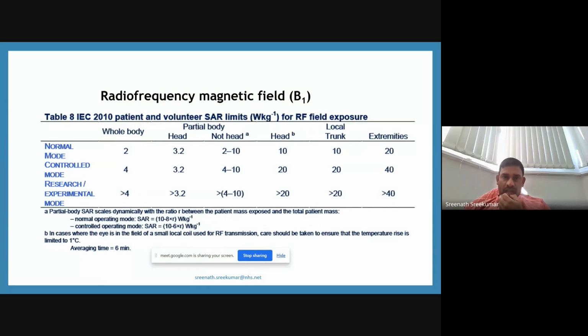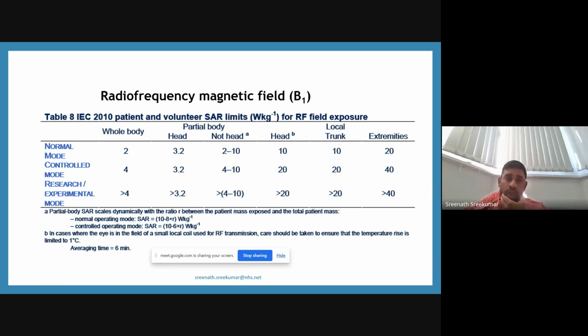So these are the radio frequency magnetic field modes. We have normal mode, controlled mode and research mode. The whole body SAR level, which is the specific absorption rate, is 2 watts per kilogram in normal mode, 4 watts per kilogram in first level mode, and above 4 watts per kilogram in experimental mode. That's the basic SAR levels for the RF pulse experienced while scanning. And the head level is always 3.2 for normal, controlled or first level.